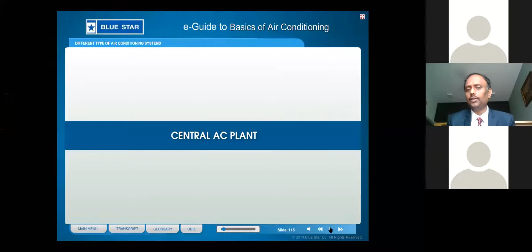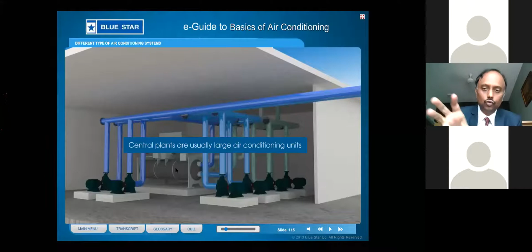The chillers are available as scroll chillers, screw chillers, and centrifugal chillers. Scroll chillers use scroll compressors, screw chillers use screw compressors, and for very large applications like airports, you have centrifugal compressor powered chillers, called centrifugal chillers.